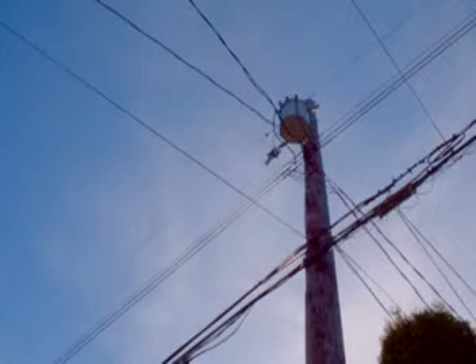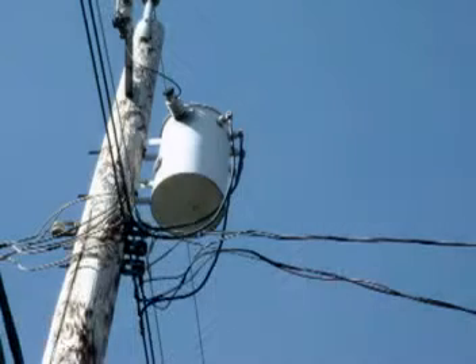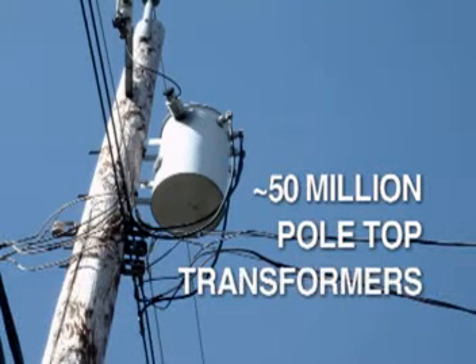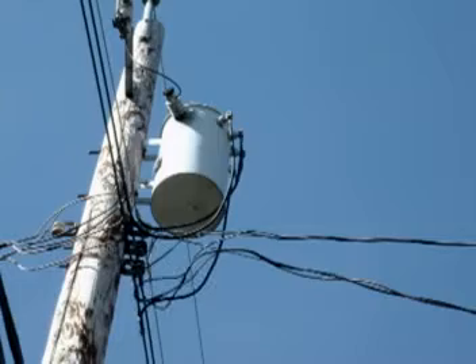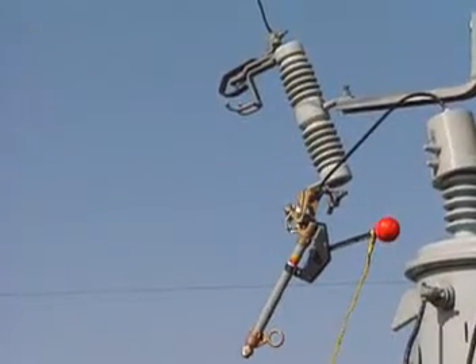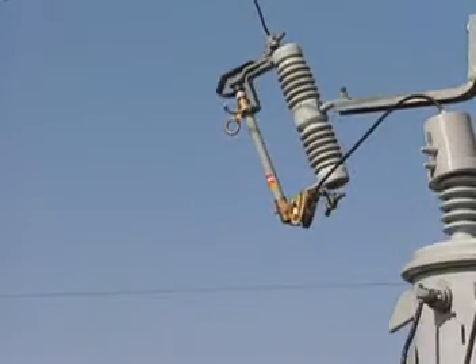Transformers are one of the most widely used components in the distribution grid. In the United States alone, there are approximately 50 million pole-top distribution transformers in service. 3 to 5% of them are re-energized every year, making it one of the most common operations for linemen.